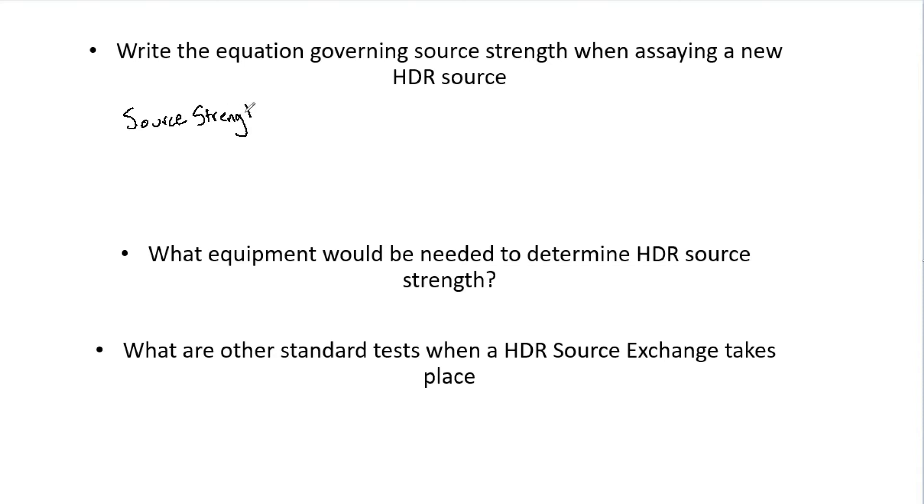So to begin, we need to know what our source strength is when we are measuring our new HDR source. To find that, we are going to use M-raw. This is the same as when you use a LINAC, it's just the uncorrected reading from your electrometer. This will be in nanoamps.